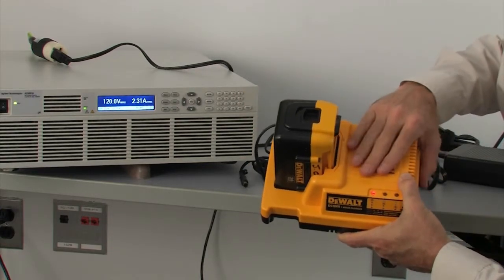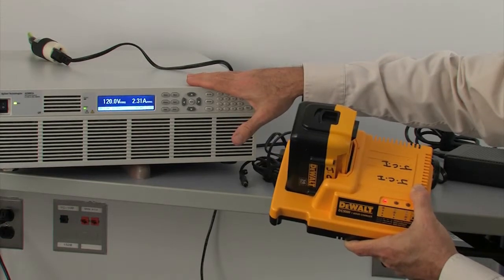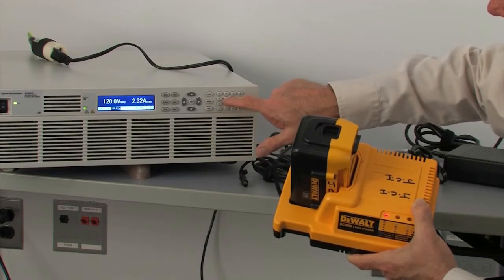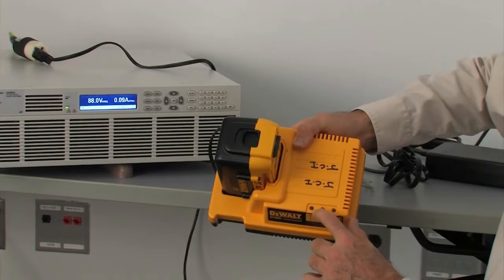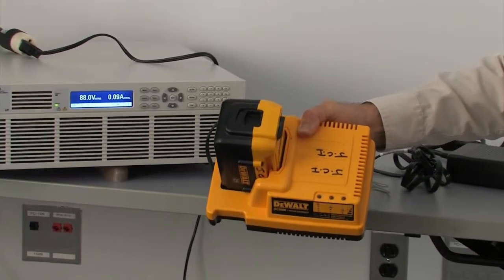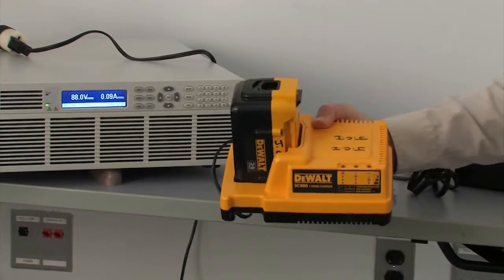So in order to test that feature of this charger, I can bring the voltage down on the output of the AC source. So let's try 88 volts, enter, and I can see that the three LEDs are flashing in the proper indication to show that there is, in fact, a problem with the power line.